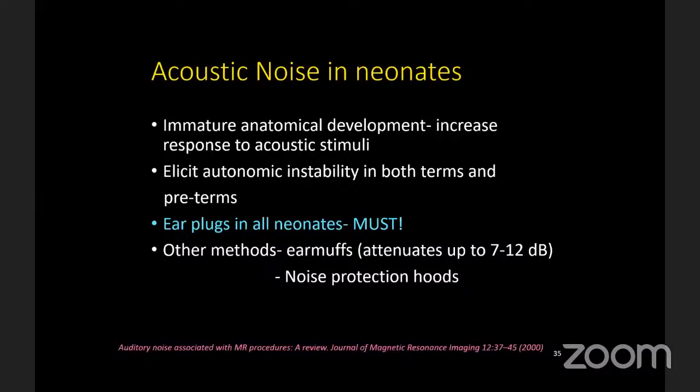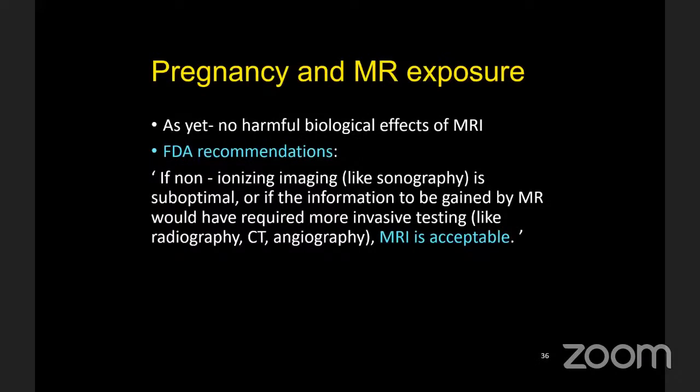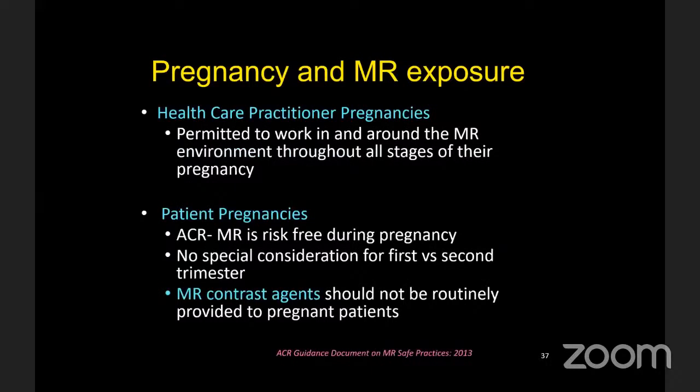Regarding pregnancy and MR exposure, no harmful biological effects of MRI have been reported as yet, but the FDA recommends MRI if non-ionizing imaging like ultrasound is suboptimal, or if the information to be gained by MR would have required more invasive testing such as radiography, CT scan, or angiography. Healthcare practitioner pregnancies are permitted to work with no issues. For patient pregnancies, MR is considered risk-free, but MR contrast agents should not be routinely administered to pregnant patients.